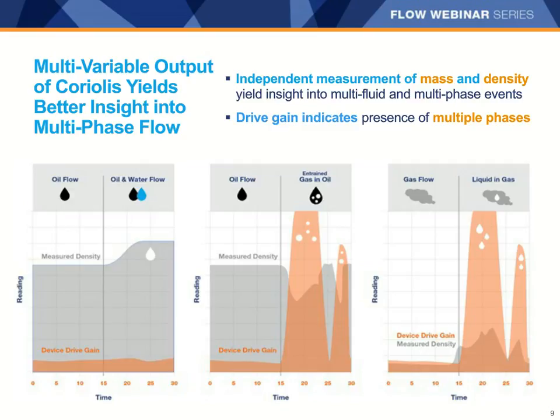Drive gain is inherently low when a meter is full with a single phase. So we'll start with the graphic on the far left, and you see your drive gain is low. It's in that peach color there. Depending on the meter size, meter type, meter construction, you can expect drive gain to either be in the single digits or up to 20%, depending on installation and type. So you expect that drive gain to be low when full with a single phase.